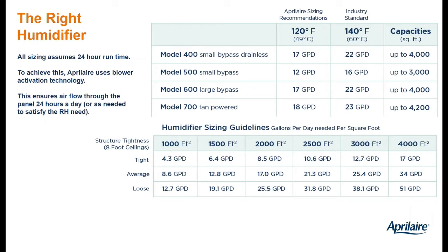Next to that, you see that some of our competition uses 140 degrees as the assumption, and we think that is not your typical furnace temperature. We think most furnaces are not that hot. And why does that matter? Going back to water, airflow, and heat, if you assume 140 degrees, you're going to think that you're going to get more evaporation out of an evaporative humidifier, whether it's ours or anybody else's. More BTUs, more evaporation. And so we think that's not doing you a favor because you might undersize the humidifier in the real world. So we're assuming a lower plenum temperature to give you a conservative estimate so you pick a humidifier that we all know is going to work well.